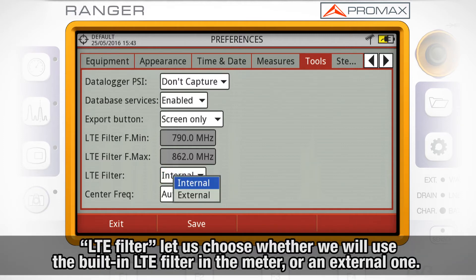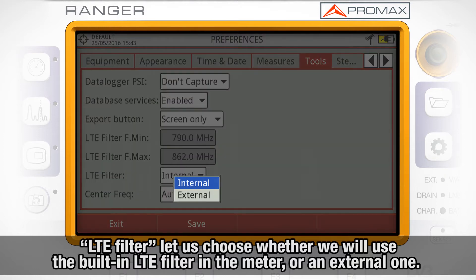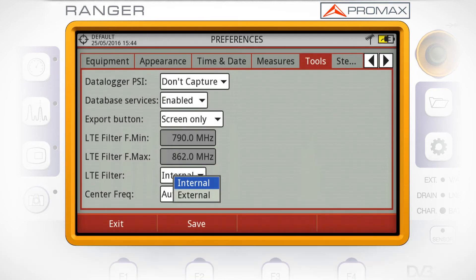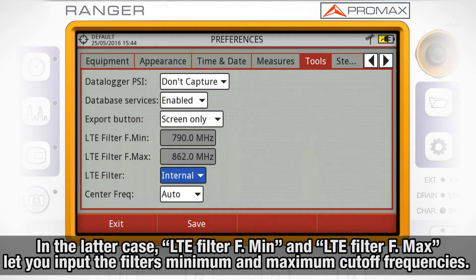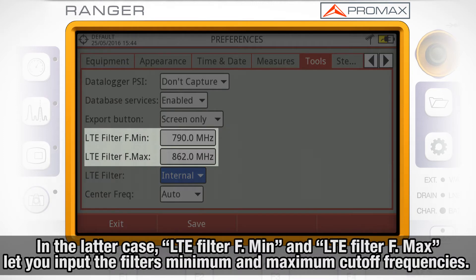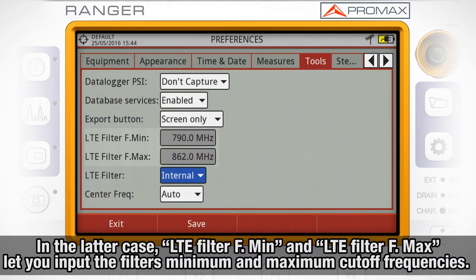The LTE filter option lets us choose whether we will use the built-in LTE filter in the meter or an external one. In the latter case, LTE filter F-min and LTE filter F-max let you input the filter's minimum and maximum cutoff frequencies.